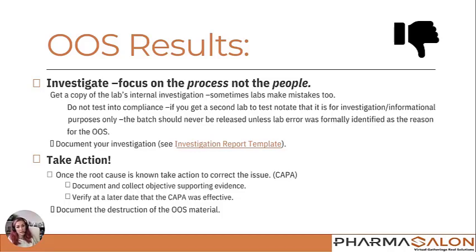Don't test into compliance. You might think, all right, I'm just going to get a second lab to test this, and it's going to be fine. You can't do that. Okay. If you have a second lab test it, that's fine. Just make sure that you notate that it's for investigational and informational purposes only.